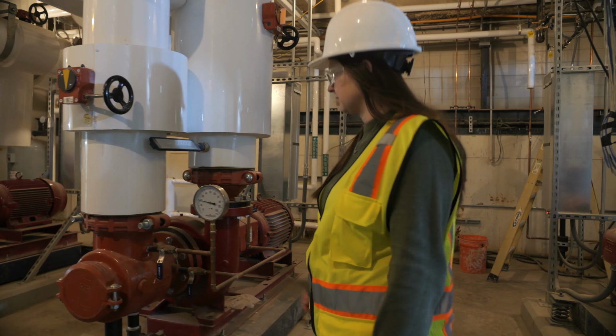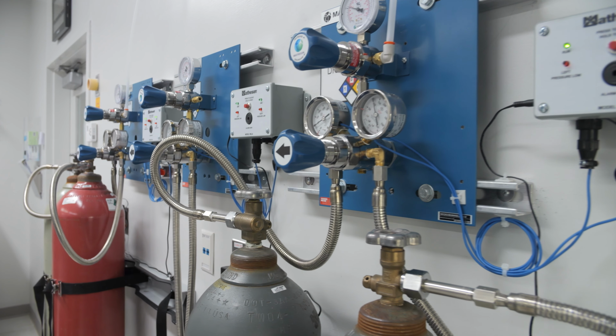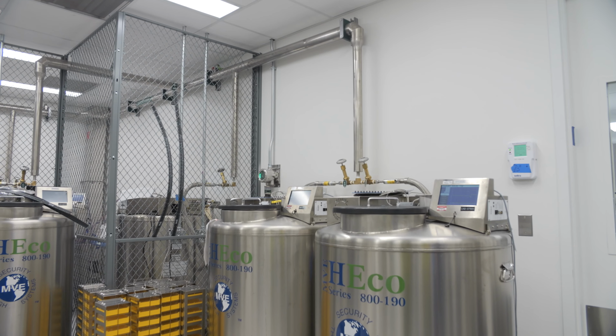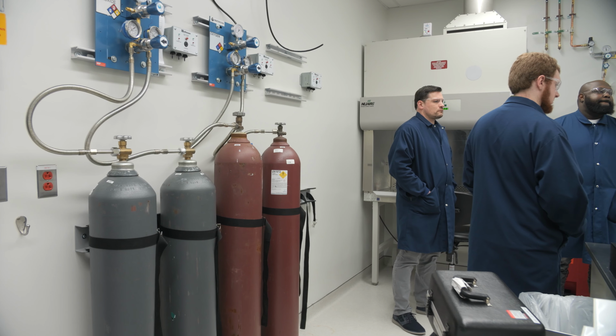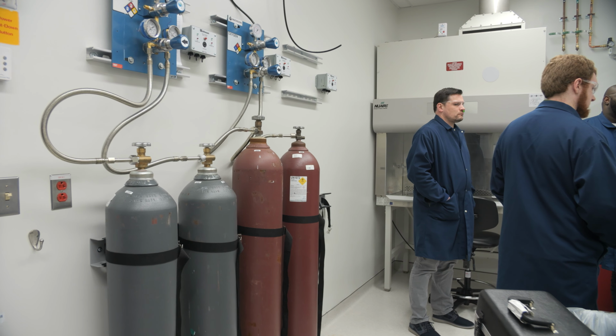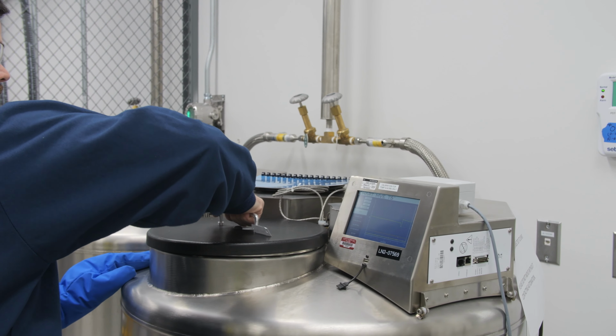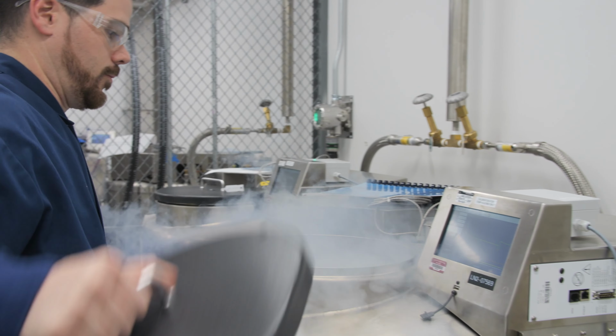The other key piece with GMP-type labs is the amount of process laboratory gases distributed around the facility to enable operations at all times — liquid nitrogen, compressed air systems, vacuum systems. The key with laboratory gases is understanding any hazard conditions we're creating, like a rupture or a leak in a tank.